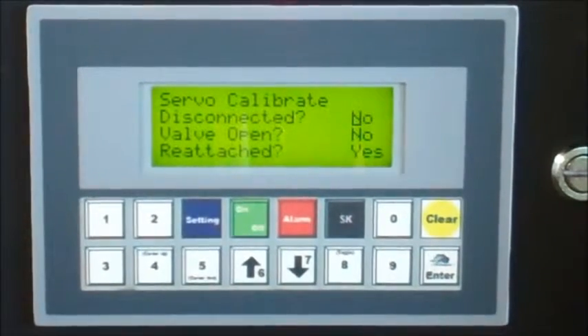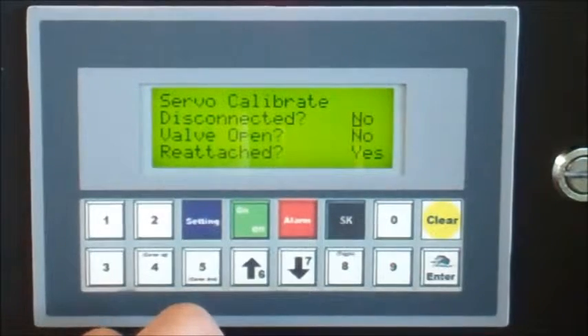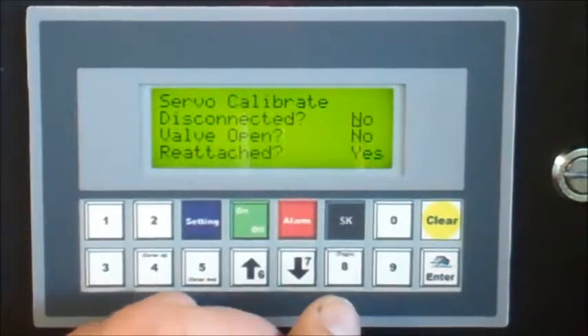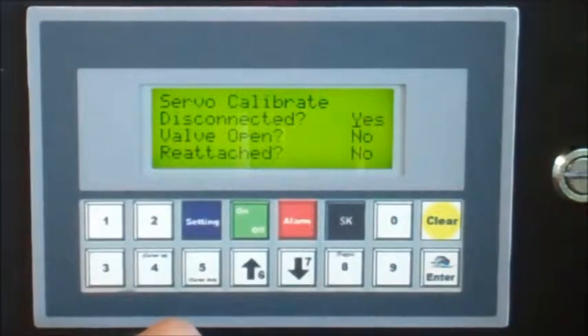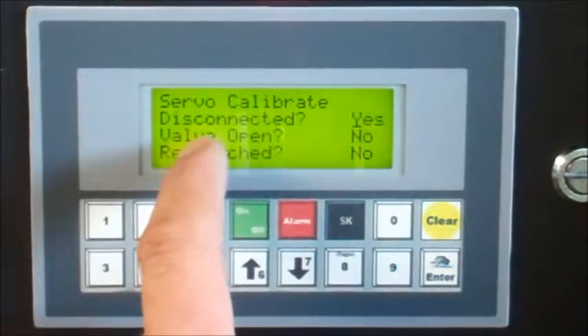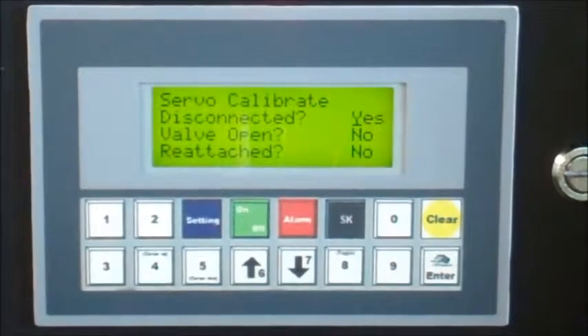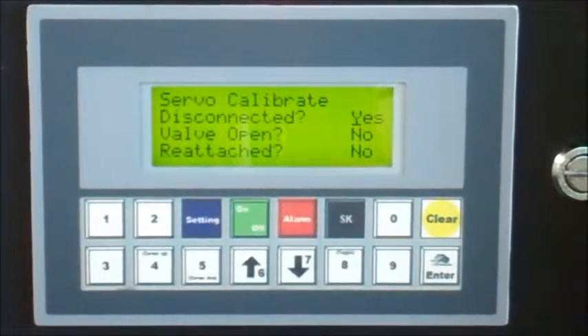The cursor is under the no for disconnected. The servo is disconnected and laying on the bottom of the cabinet. You will toggle that to yes. And at this point it will ask you if the metering valve is open. That is when you'll turn the metering valve all the way counterclockwise until it stops, and then just bump it off of the jammed all the way open point.